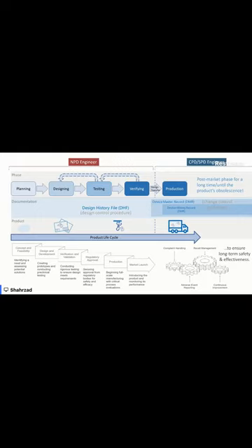Whereas after market launch, the CPD, or commercialized or sustainability product development engineer, would be using design history files. However, they would also handle and create device master record and device history record files, DMR and DHR.